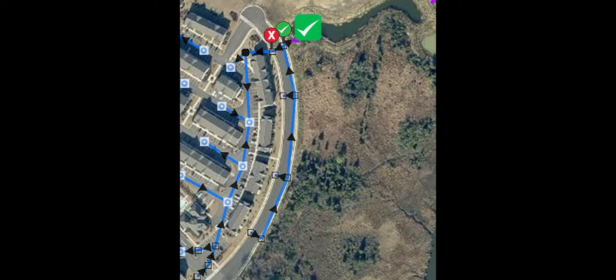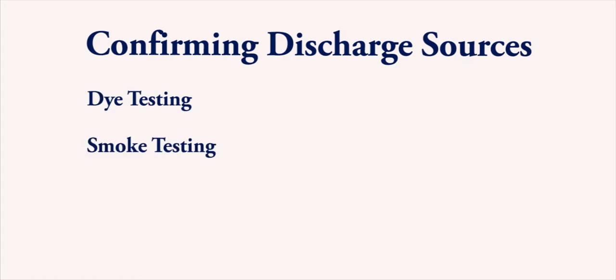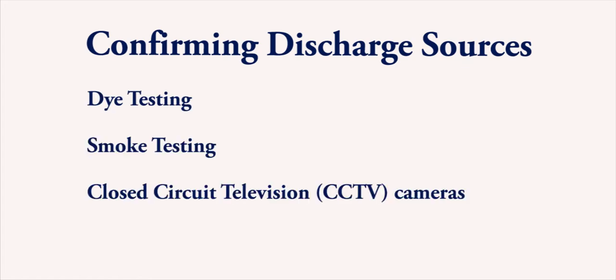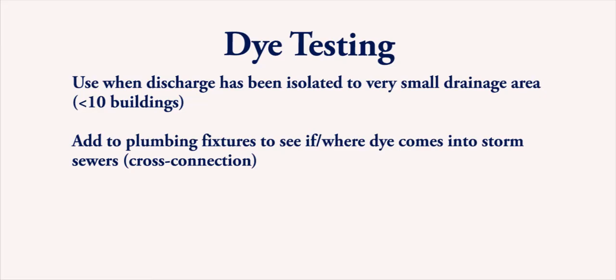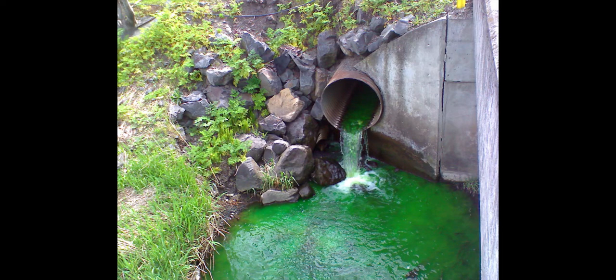Once you have narrowed down the discharge to a specific point in the pipe system, you can use a number of techniques to confirm the actual source. These include dye testing, smoke testing, and closed circuit TV or CCTV cameras. Dye testing is useful when the discharge has been isolated to a very small drainage area with fewer than 10 buildings and the suspected discharge is a sewage connection to the stormwater system. Dye is added to plumbing fixtures to see if and where the dye comes into storm sewers, confirming a cross connection.